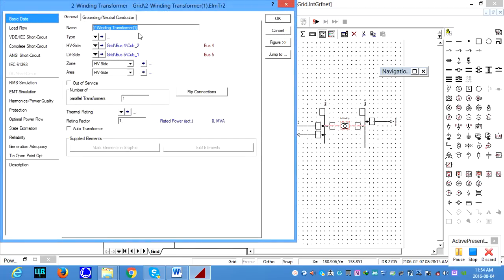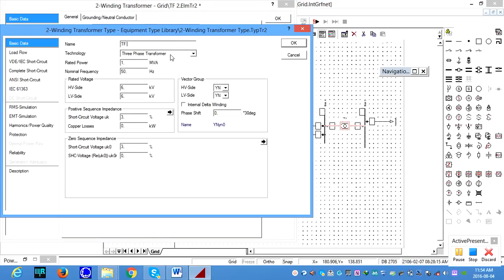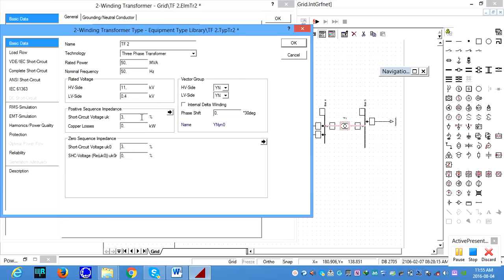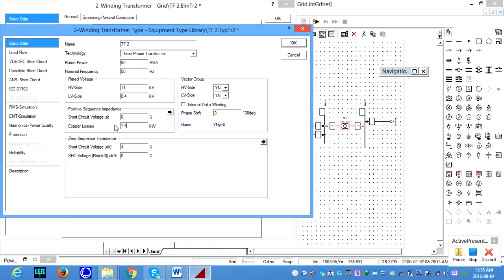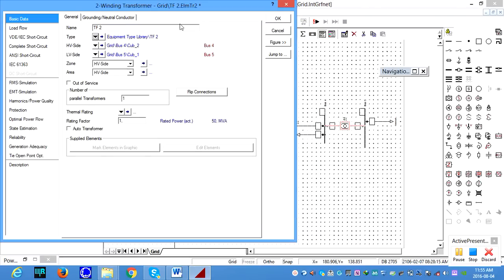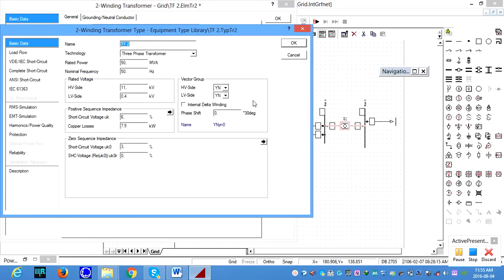For transformer 2, we can say short name TF2. And you go to the type, you select a new project, and we change the name to TF2. And the rating for transformer 2, the MVA is 50 MVA. And the HV side, I think this transformer is going to step down 11 kV to 400 volt. Okay. And the short circuit ratio is 6%, and the copper losses is 7.5 kilowatt. Okay, the rest we are happy, and the vector group is YN, we leave it as default. Okay, if you want, you can double check and make sure the data are according to the table 1.3.